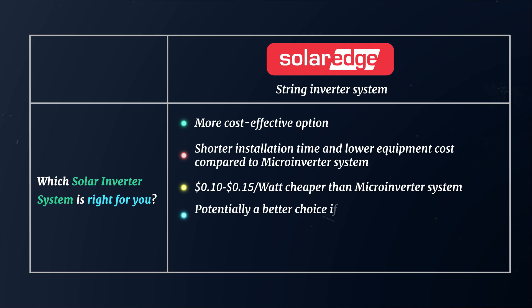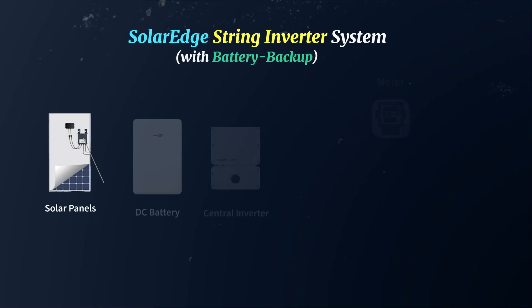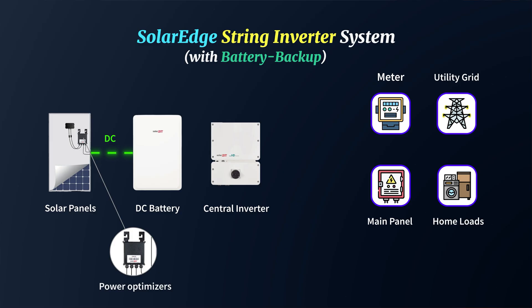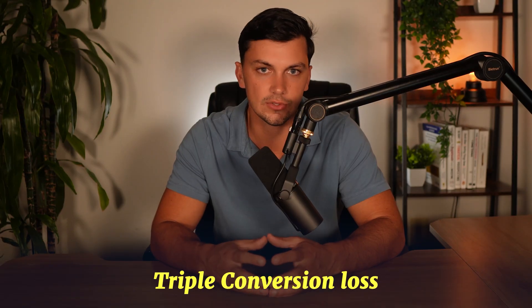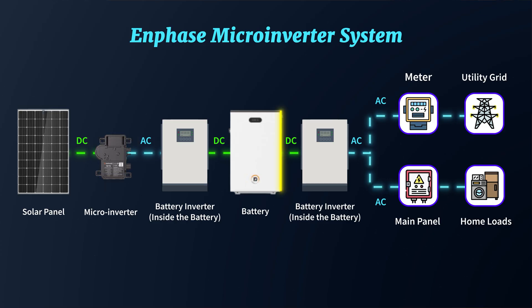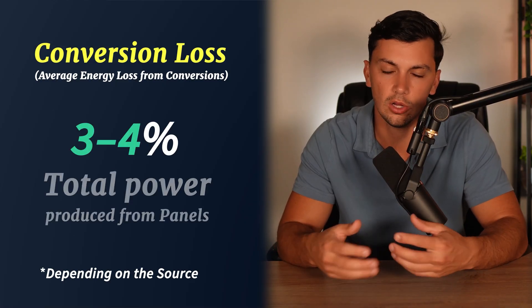SolarEdge also stands out as potentially a better choice if you plan on incorporating a large battery backup storage system into your project. Since all batteries store energy in direct current — DC — a SolarEdge system works seamlessly by allowing the panels to generate power in DC, which can then go directly into charging the battery without requiring an additional conversion. With an Enphase system, however, this process looks different. While the batteries still store power in DC, the Enphase system converts the power to AC immediately on the roof using the microinverters, leading to what we refer to as the triple conversion loss. The panels generate DC, the microinverters convert it to AC, then the battery converts that AC back to DC to store the energy, and when the stored power is needed, it's converted again from DC to AC for use in the house. The average energy loss from these conversions is about 3 to 4% of all the power produced from the panels.